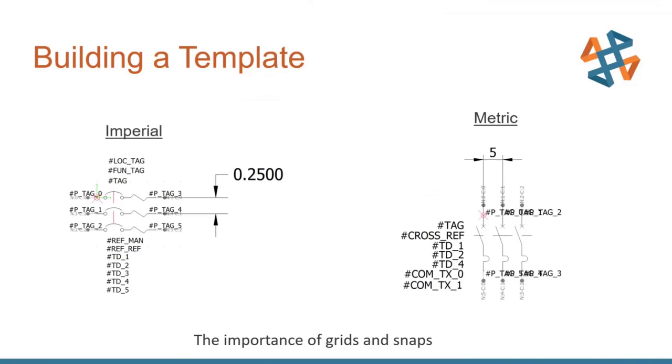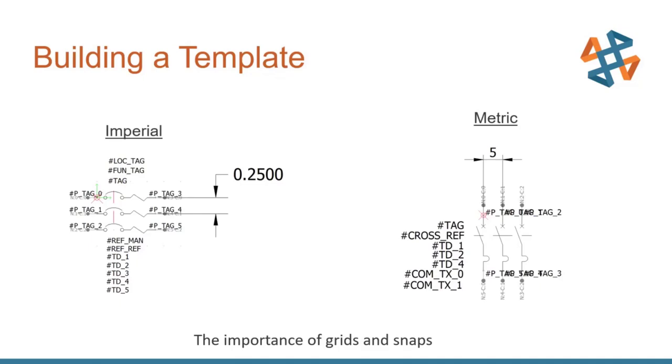So next thing with building your template is, again, standardizing your symbols. There are two standards that are available in online content. The first is if you're using imperial, most connection points will be at a spacing of 0.25 inches. Now you can use a multiple of that if you want to use 0.125 for PLCs. That's fine, but it's that standard spacing. Next is metric symbols. That's typically an online content going to be provided to you at five units for that metric space. So my recommendation is to follow one of those two standards. You can create your own custom standard. That just means whenever you download online content, you'll have to scale it appropriately.